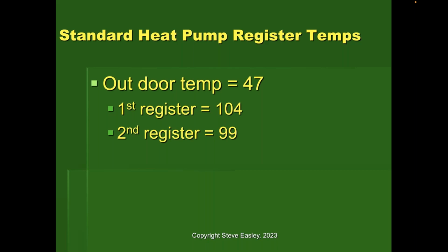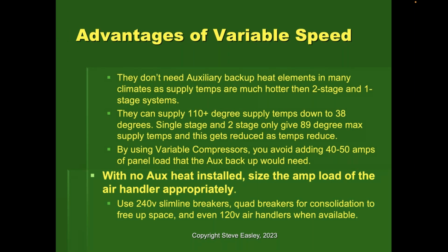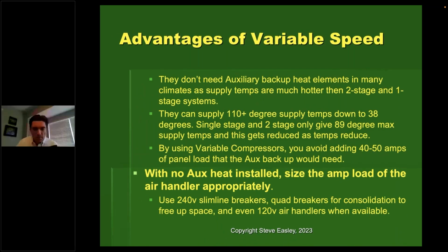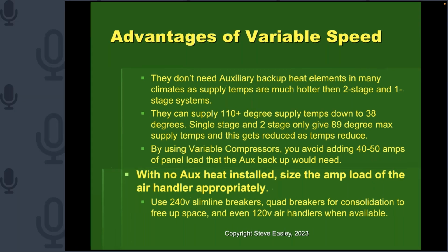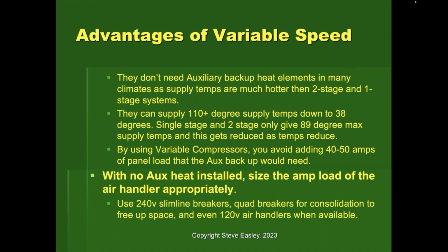But my point is that even with the outdoor temperature at 47 degrees, the hottest my register temperature coming out of that ductwork is 104. The newer, more efficient equipment can get much higher performance. So just to review, the advantage of the new variable speed inverter-driven heat pump systems is that typically they don't need auxiliary heat backup. Not to say that you don't need emergency heat, but typically you don't need auxiliary heat backup elements.